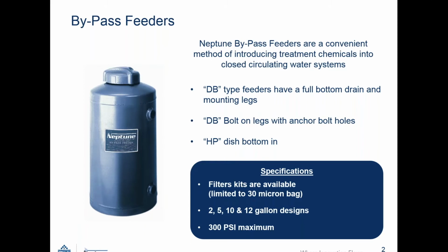The bypass feeders. Bypass feeders is one of the more popular items that we have on the water treatment side. We have bypass and filter types. They're a convenient way of introducing chemicals into closed circulating water systems. You're basically removing the top cap and you're introducing the chemical into the tank and letting the water that's in the system flush it through the tank and into the system. We have a few different types.